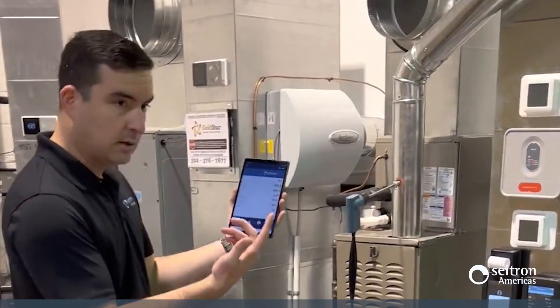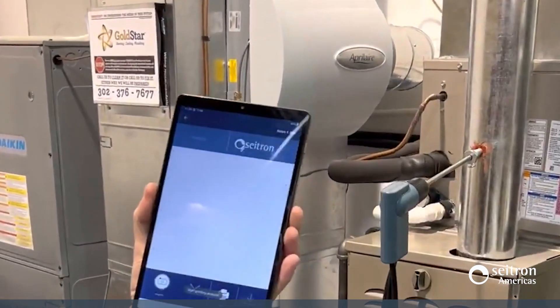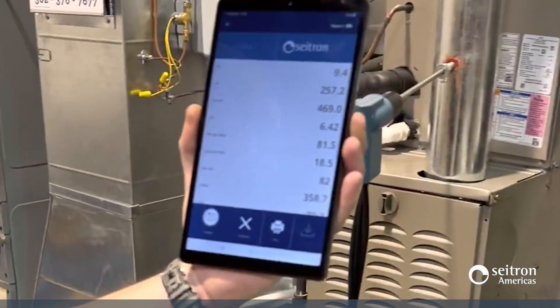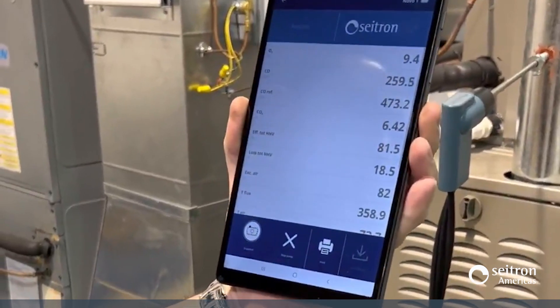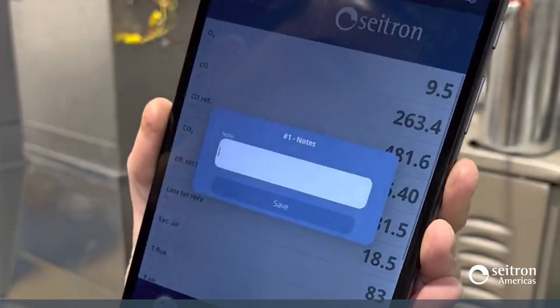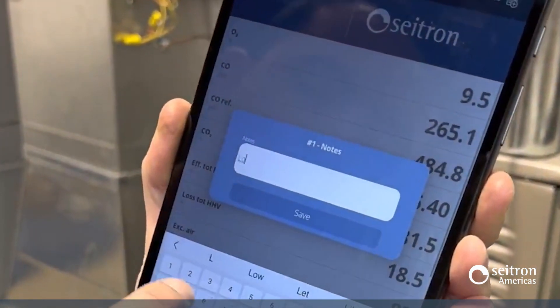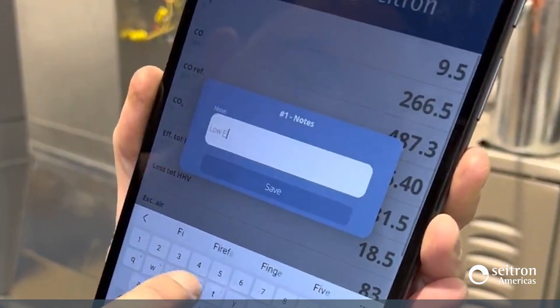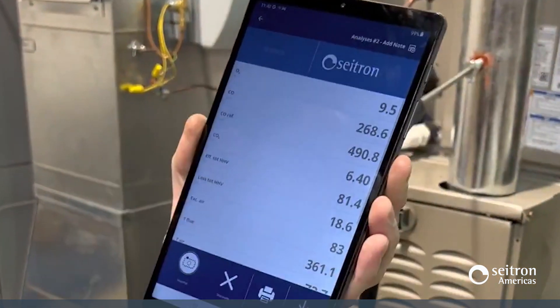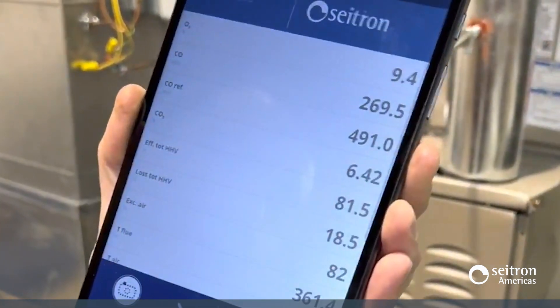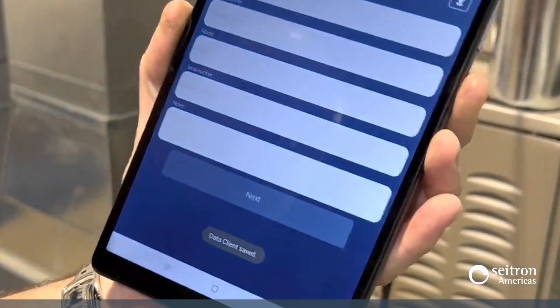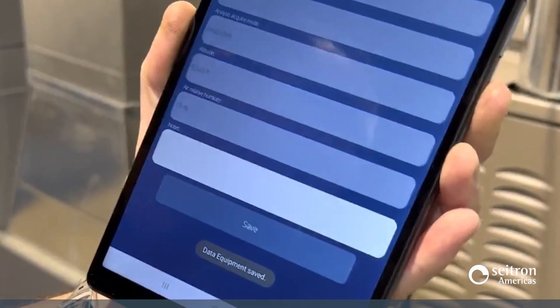From the app, you can remotely print directly to the combustion analyzer. You also have the ability to save multiple snapshots — for example, if you're doing a low fire and high fire test, you can hit snapshot and add a note associated with that particular snapshot, such as 'low fire.' You can make as many snapshots as you want, add additional notes, save your analysis, and once again create a digital report by entering the customer's information, equipment details, and your own information to generate a PDF or Excel file.